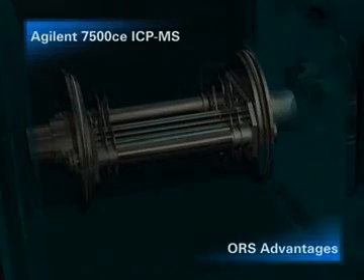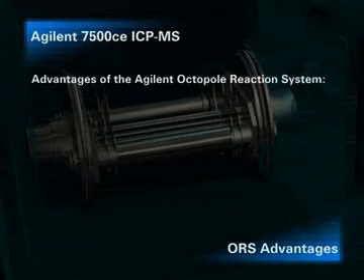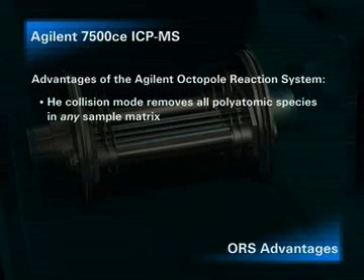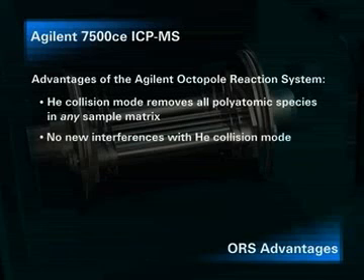The Octopole reaction system offers the analyst a number of advantages. Its unique helium collision mode removes all polyatomic species simultaneously. No prior knowledge of the sample matrix is required. Unlike reactive cell gases, pure helium cell gas is inert and does not react with the analyte or sample matrix. Reactive gases are not suitable for multi-element analysis in complex sample matrices, since they react with the sample matrix, forming new interferences in the cell, which can bias analytical data.